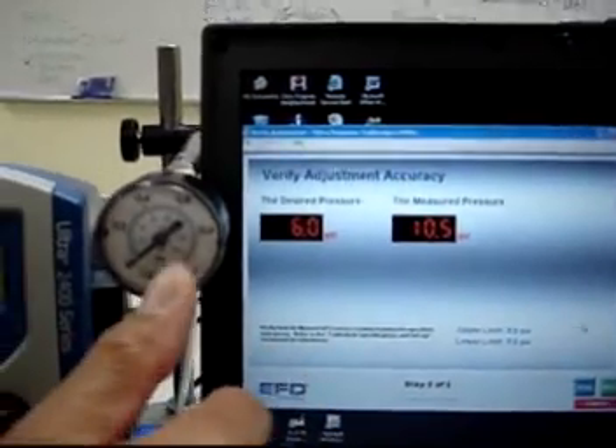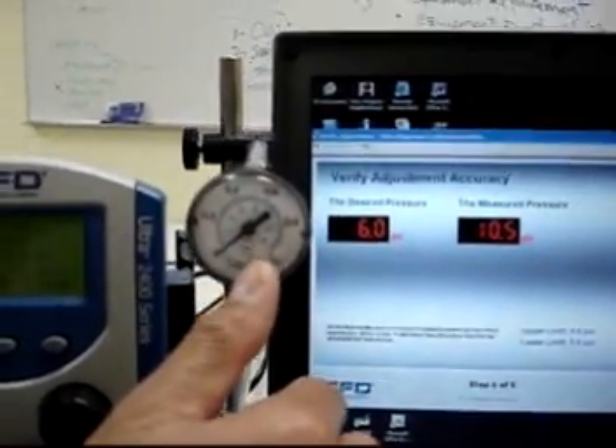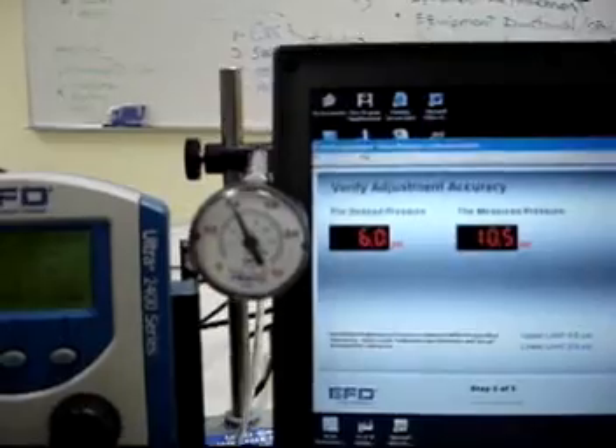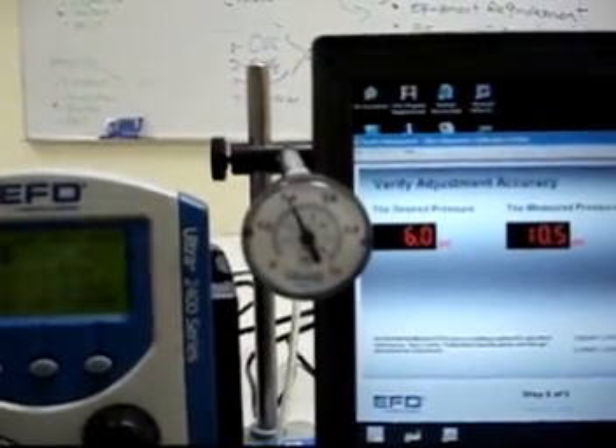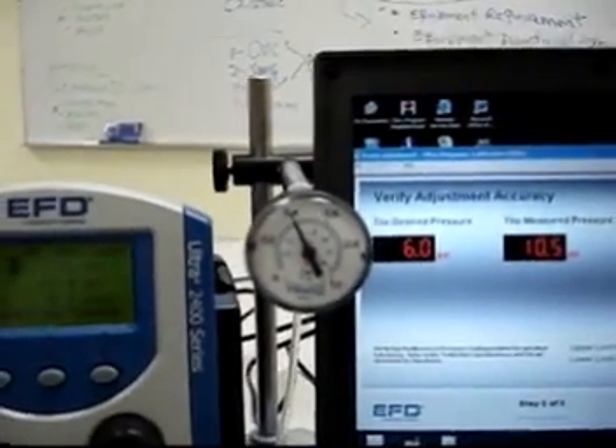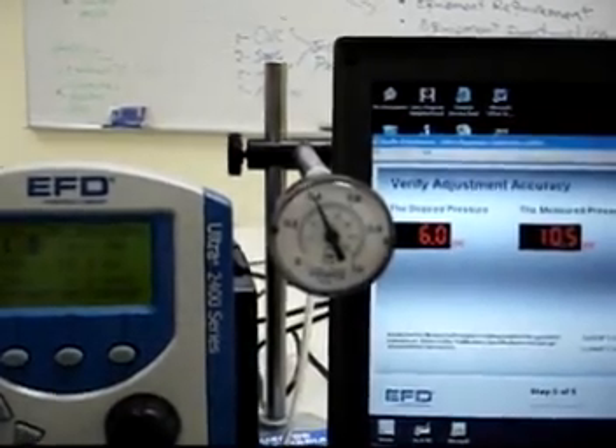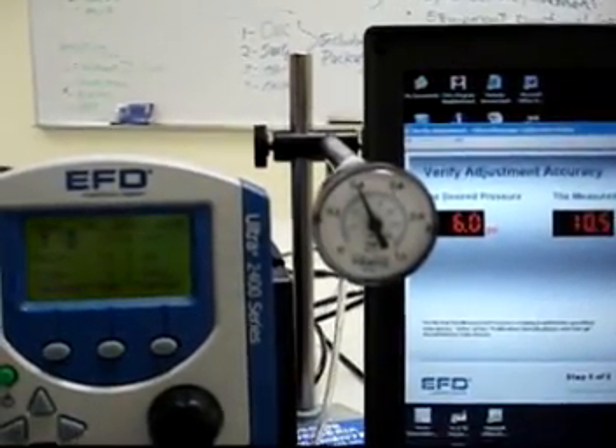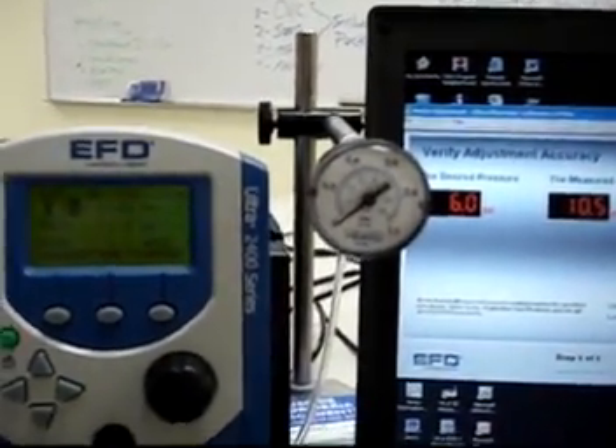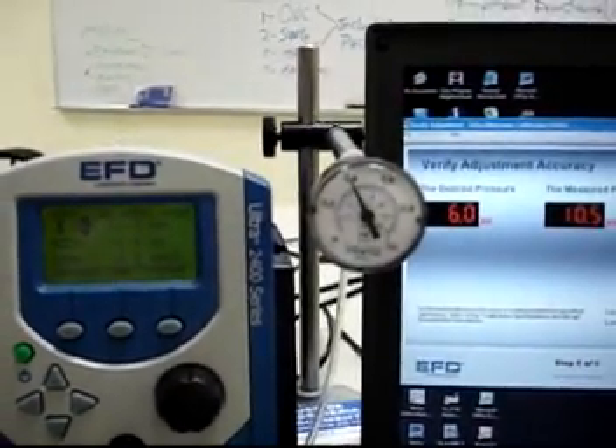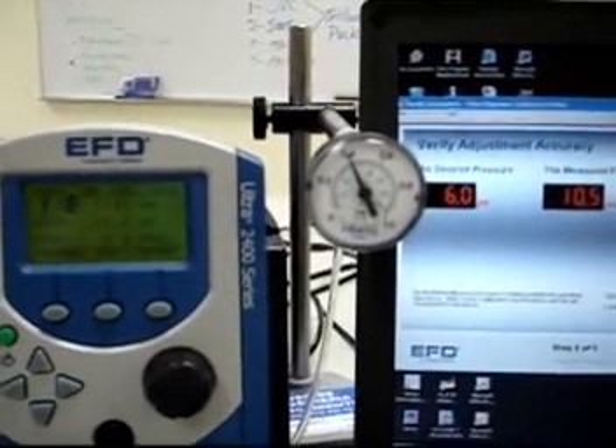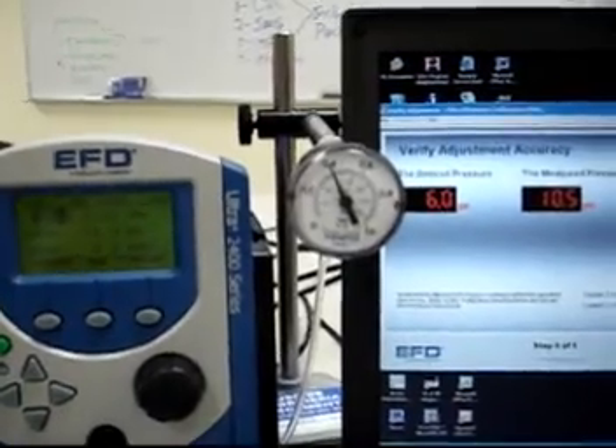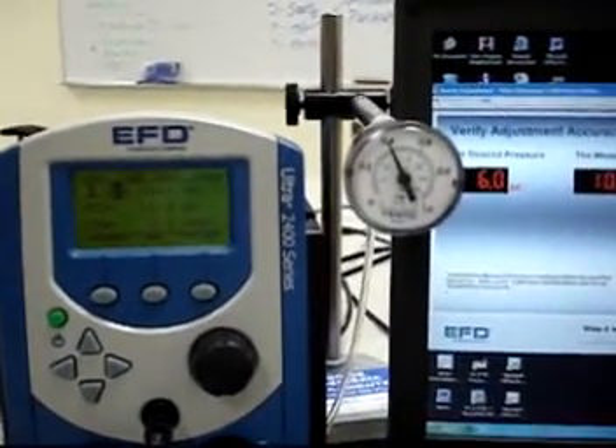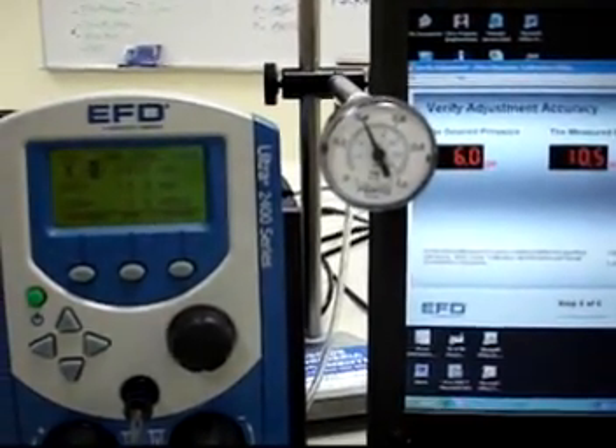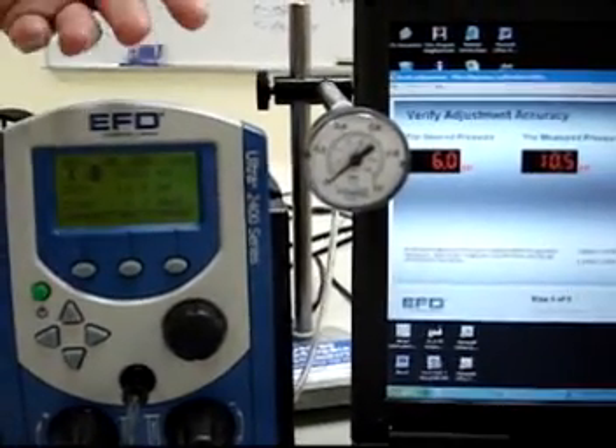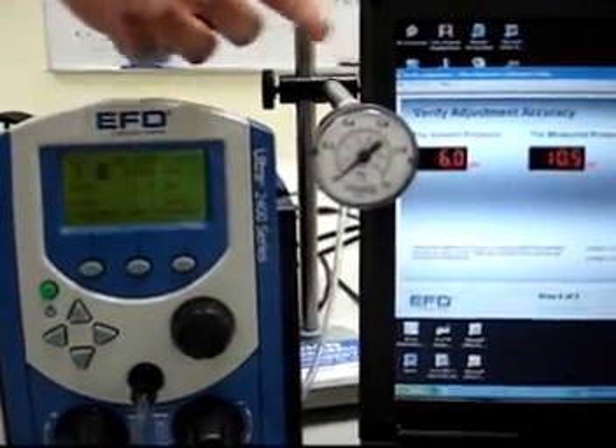But this is my calibrated gauge, I believe, on this one. It's saying 6, and the software tells me 10.5. The machine is telling me 10.5. I can repeat this as many times as I want, and I will have the same result. I'm not able to make the machine tell me the same as my gauge.